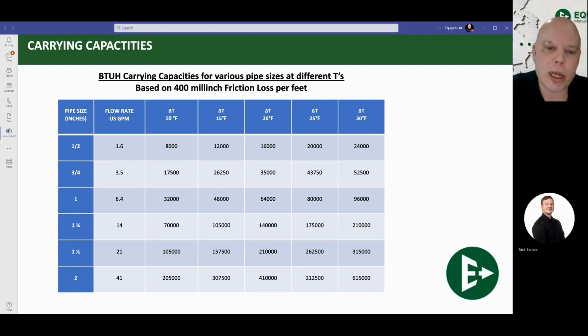So I'm going to go back and I'm going to pick on that 100,000 BTU boiler. Now on the left of this chart, you have pipe size. Across the top, right after flow rate, you have delta T. As I mentioned before, your standard delta T's that you're going to find in a system is going to be 20 degrees for radiators, air handlers, indirects, everything like that. So we're going to pick on the 20 degree delta T. With a 100,000 BTU boiler at a 20 degree delta T, what size pipe do I need to carry that heat?